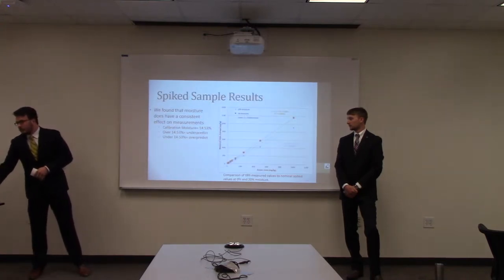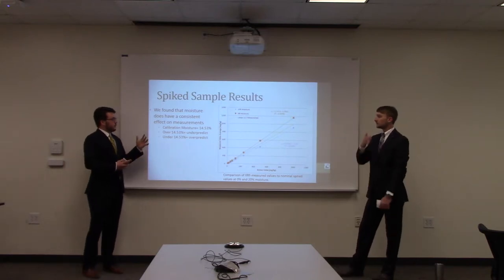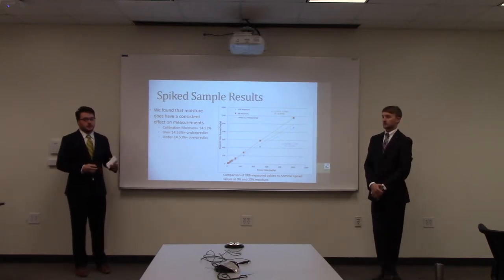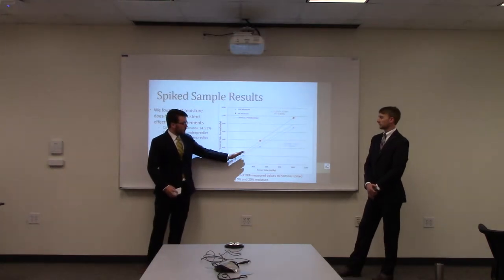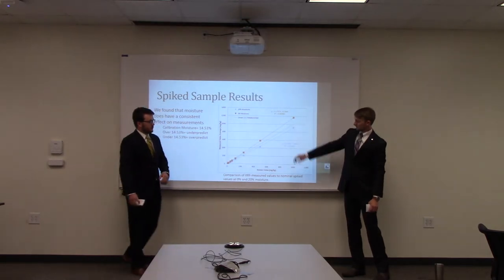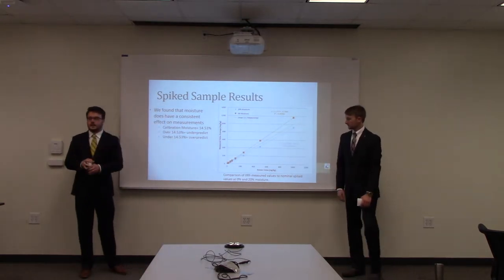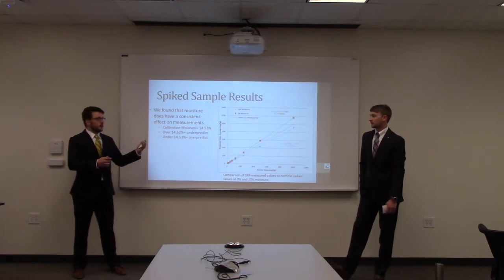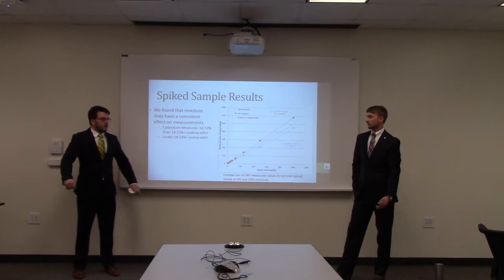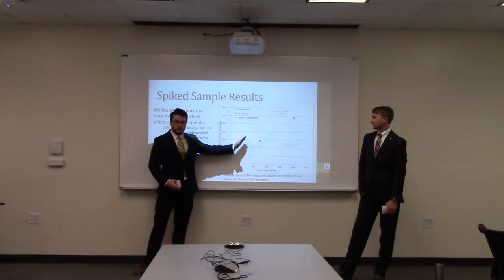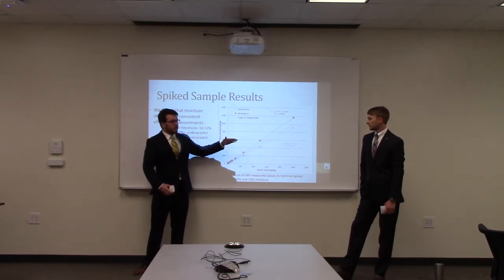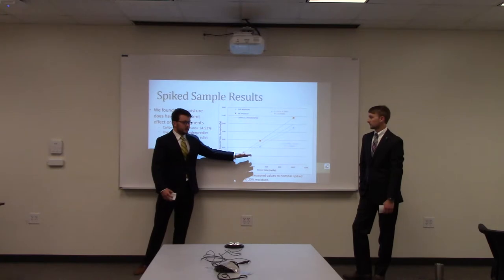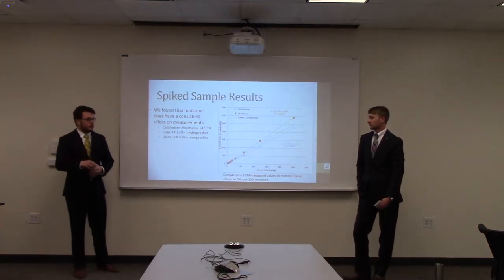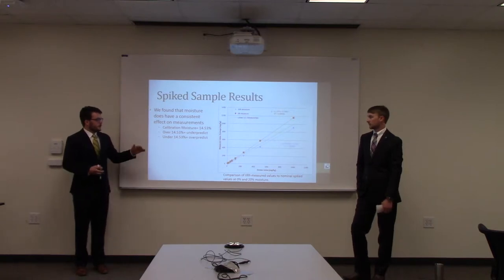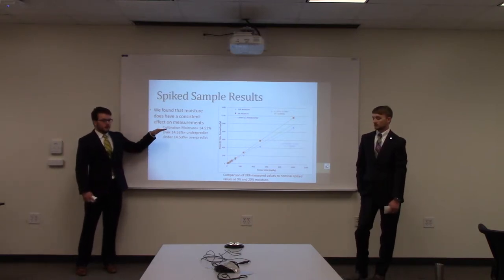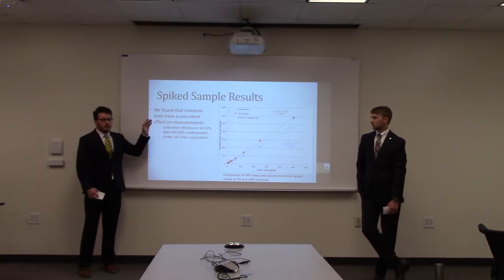So we ended up having our results of that study, and found that we were having a consistent overprediction or underprediction. Ideally we would have our green line, that's the ideal, saying that if there's 10 milligrams per kilogram of mercury there, then that's what we were shooting for. But we were actually, for 0% moisture, consistently overshooting that a little bit. And then whenever we brought it up to 20% moisture, we were actually undershooting it. So that was the consistency going on with each sample we were doing. Basically, whether we were above or below our set calibration moisture was determining whether or not we were over-predicting or under-predicting it.